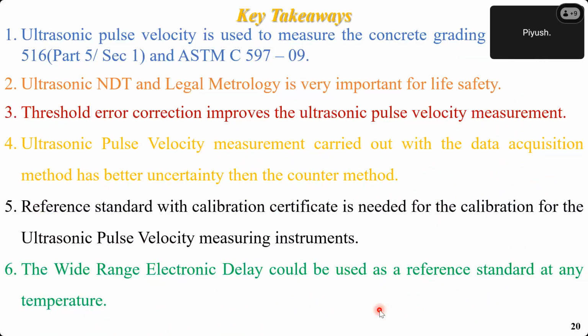These are the key points of our seminar. Ultrasonic pulse velocity is used to measure concrete grading as per IS 516 and ASTM C597. Ultrasonic NDT and legal metrology are very important for life safety, as we have seen in our slides. Threshold error correction improves the ultrasonic pulse velocity measurement. Measurement carried out with the data acquisition method has better uncertainty than the counter method. We require certain reference materials for the calibration of ultrasonic pulse velocity measurement instruments, and we can use a wide range electronic delay as the reference standard at any temperature.